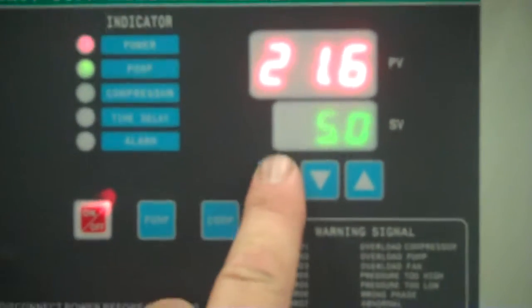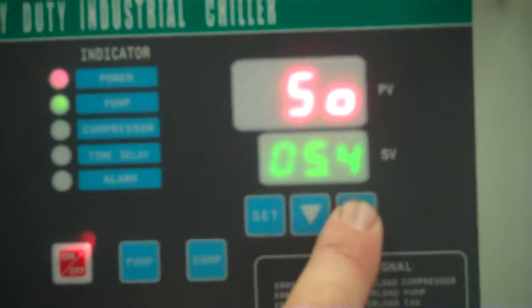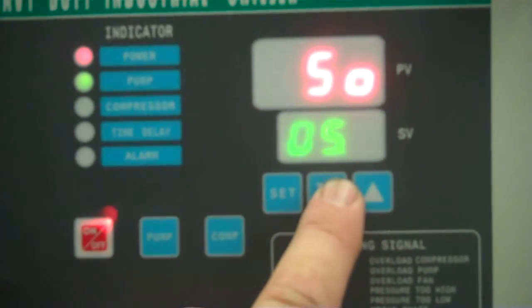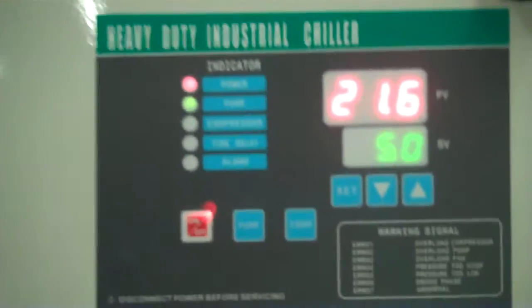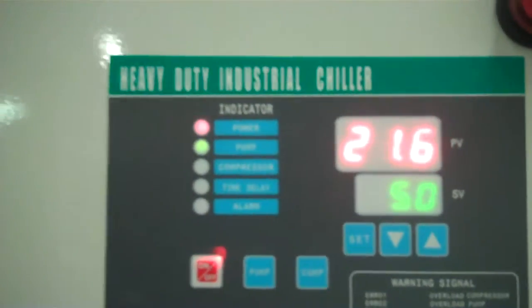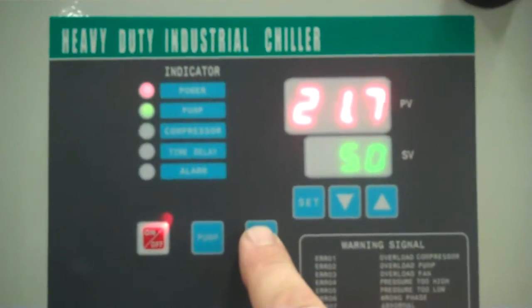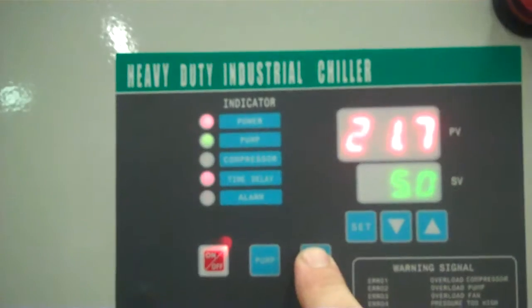And we have the set point of the chiller. Go up and down. The lowest you can go is 5 degrees centigrade, and that's what we're going to set it at. To start the chiller next, you press the compressor button, COMP, and you'll see that little time delay came on. There'll be about a 90-second time delay before the fan and the compressor start.